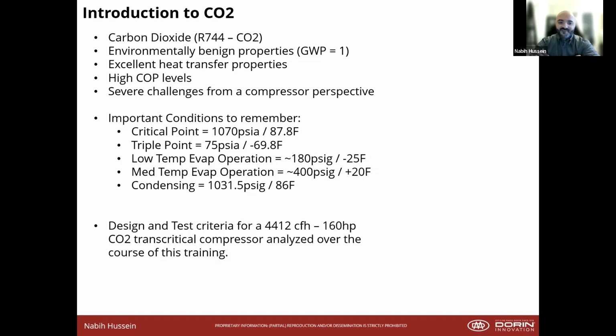Low temp evap operation is usually around 180 psi, negative 25 F. Medium temp is around 420 psi. So for operators, those are the conditions you would keep in mind. And condensing happens at 1031.5 psig and 86 F. Just some things to keep in mind, and all the design and test criteria I discuss in this presentation is based off of our 4412 CFH 160 horsepower compressor. It was our largest until we made a larger one.